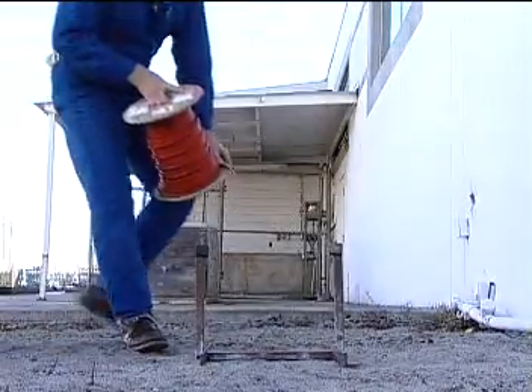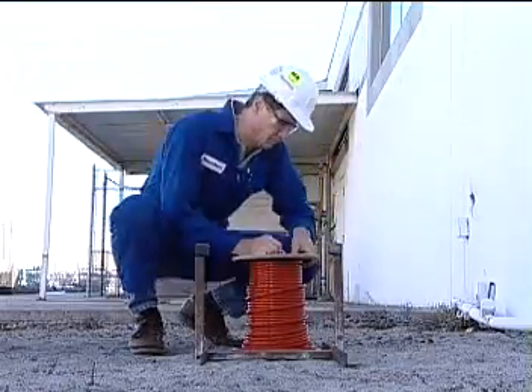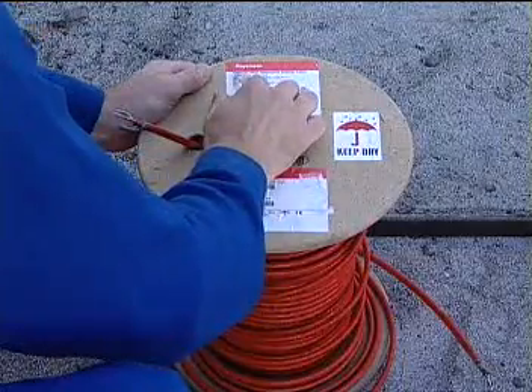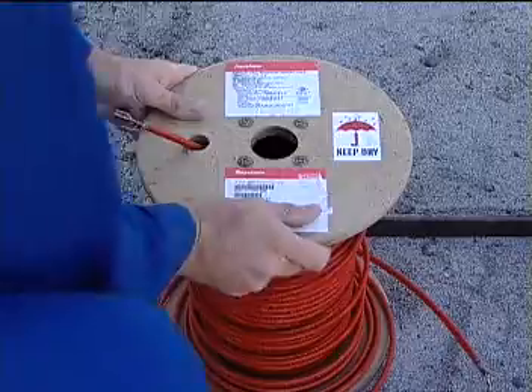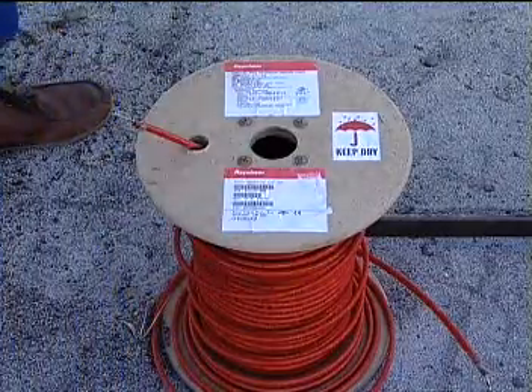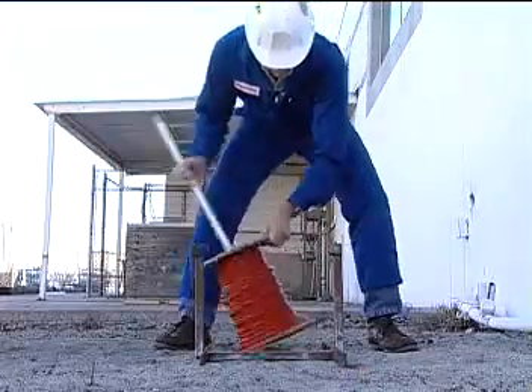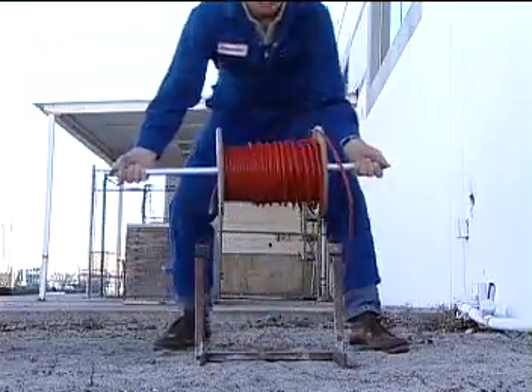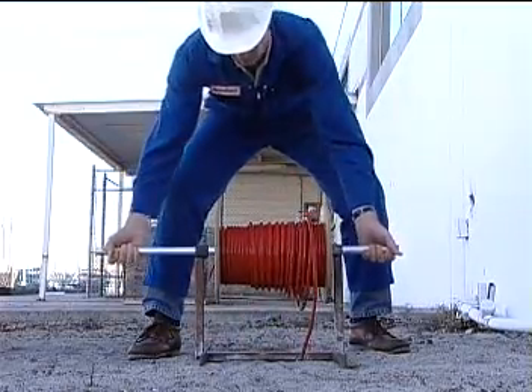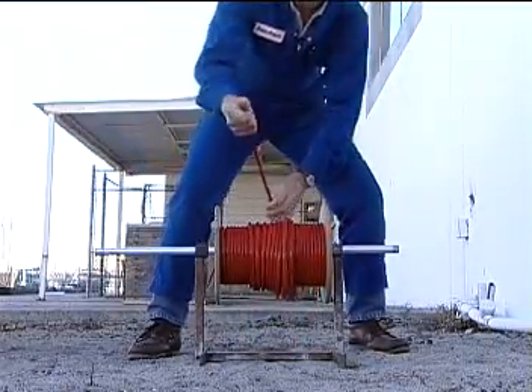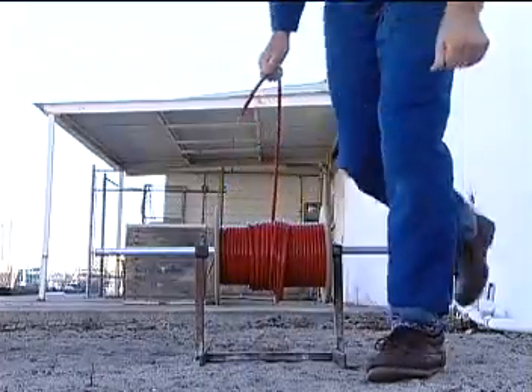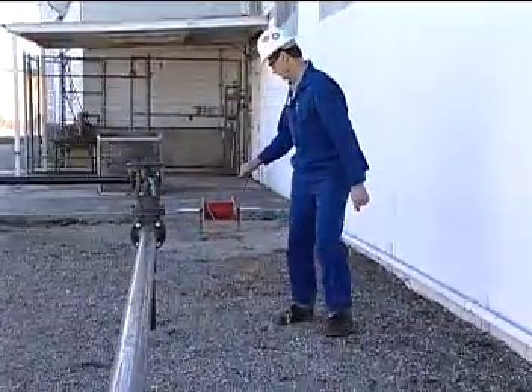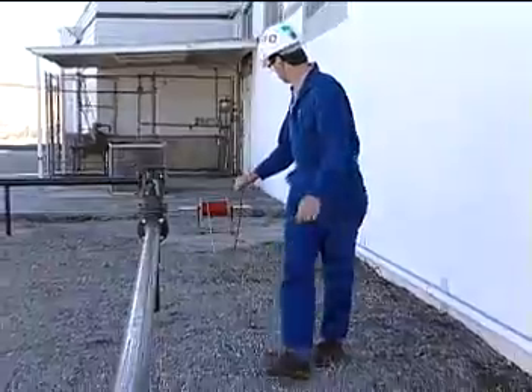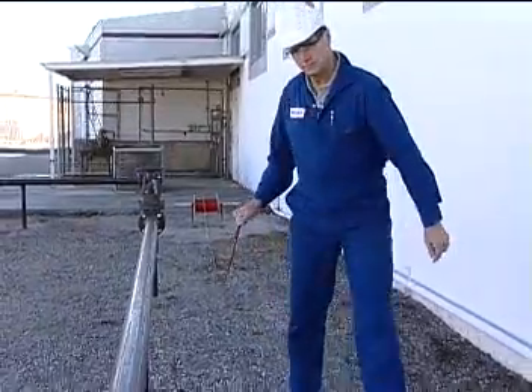Before installing cable on the pipe, take a moment to re-verify that the cable you are about to install has the correct rating for the power, environment, and temperature of the application. If everything is correct, mount the reel on a stand near the start of the circuit. This will make it easier to pull the cable along the path of the pipe. Pull the cable the entire length of the pipe to the point where it will be terminated. This is an effective way of making sure that you have enough cable for the entire circuit.